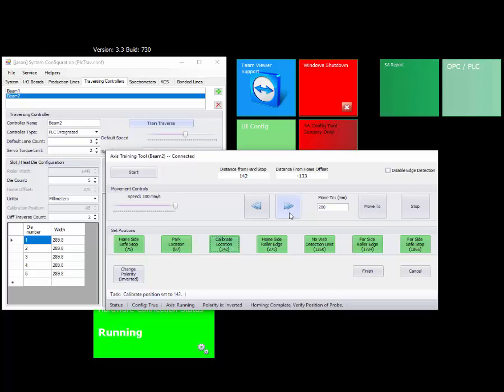The next thing that they're going to do is move the probe head until the center of the probe is lined up directly with the edge of their physical roller on that machine. We're setting up a physical machine. This is not setting up to a web that may have different sizes. So we want to get to the physical limit of where a material can possibly be made or reach to.